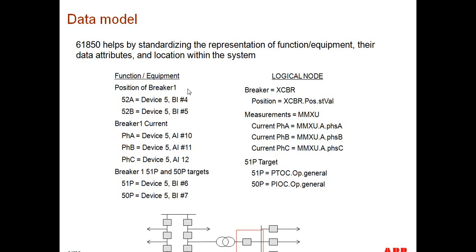So you can see that if your substation grows and grows, you're going to have a whole bunch of devices, different device numbers, and different binary input numbers. Without some sort of reference list that ties this protocol-based information to the application or the substation, you wouldn't really be able to know that that is the position of a breaker. Whereas in IEC 61850, the position is presented as the IED name, dot, the logical node, dot, the particular data object and data attribute being presented. And this results in a protocol structure whose meaning is tied to the protocol definitions.